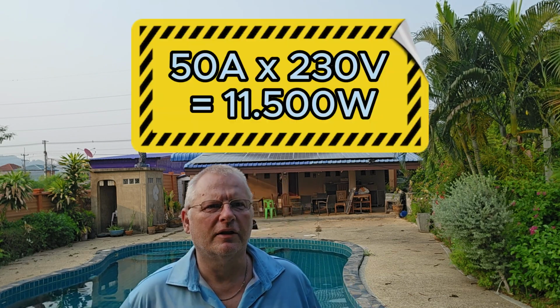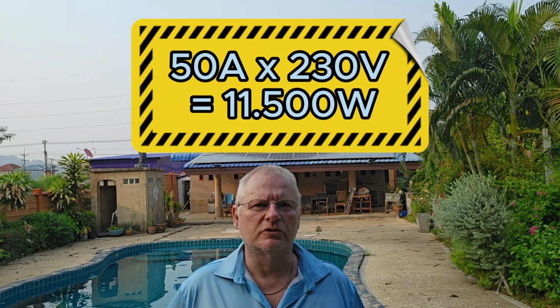You have an amp rating, so let's say you have a 50 amp volt regulator. In a normal volt situation, that volt regulator will support about 11,000 watts. The problem is that when the volt regulator is actually performing its function, the voltage is much lower. So you have to calculate that before you buy, and actually measure how low your volt goes before you buy a volt regulator. The lower the volt goes, the higher the amp needed, so if your volt problem is really bad, you need a very big volt regulator.